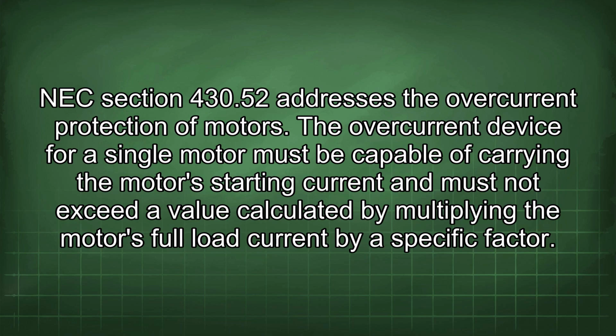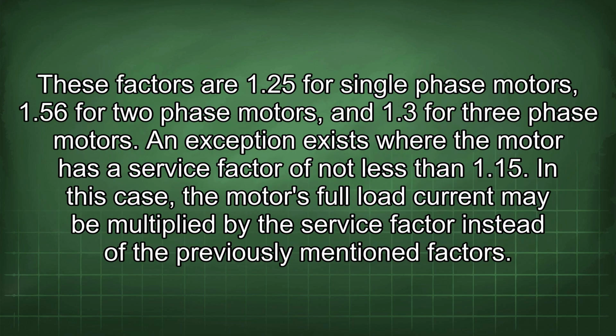The overcurrent device for a single motor must be capable of carrying the motor's starting current and must not exceed a value calculated by multiplying the motor's full load current by a specific factor. These factors are 1.25 for single-phase motors, 1.56 for two-phase motors, and 1.3 for three-phase motors. An exception exists where the motor has a service factor of not less than 1.15. In this case, the motor's full load current may be multiplied by the service factor instead of the previously mentioned factors.